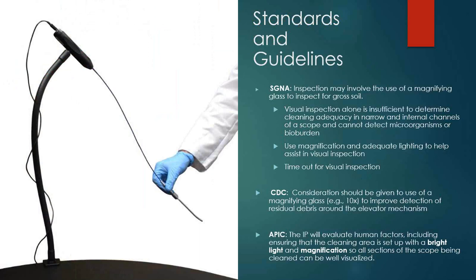SGNA states inspection may involve the use of a magnifying glass to inspect for gross soil. Visual inspection alone is insufficient to determine cleaning adequacy in narrow and internal channels of a scope and cannot detect microorganisms or bioburden. Use magnification and adequate lighting to help assist in visual inspection.